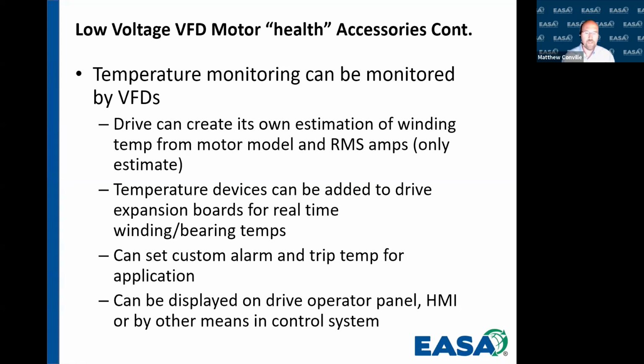What I mean by that is, let's say, for instance, we have a bearing, and the bearing is good for 80 degrees centigrade for an alarm and 100 degrees C for a trip, which would be about 212 degrees Fahrenheit for a trip. And we're constantly operating somewhere in the ballpark of about 100 to 130 degrees Fahrenheit. So we may not want to set an alarm at 170 to 180 degrees Fahrenheit. We may want to set it lower, because over time we've seen that the bearing never gets that warm. If the bearing starts to get that warm, then we know that we have a problem.